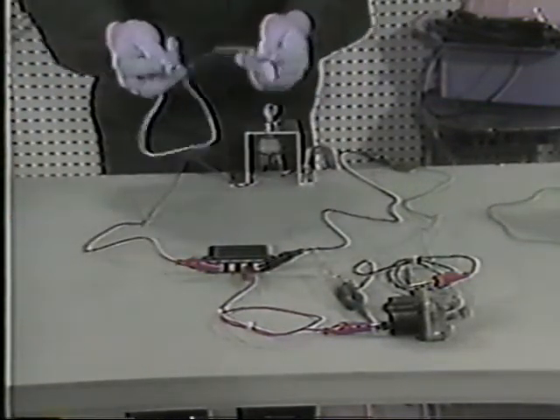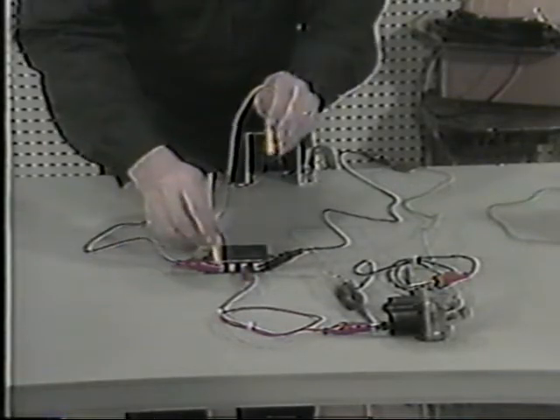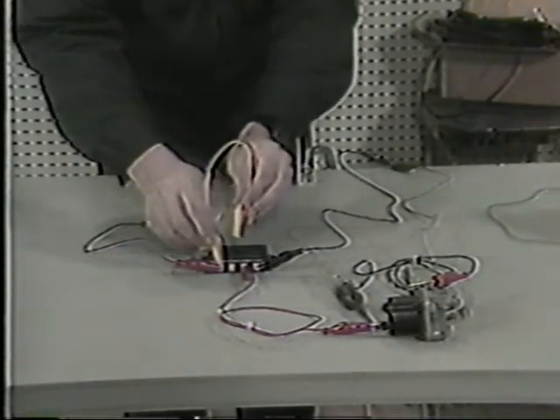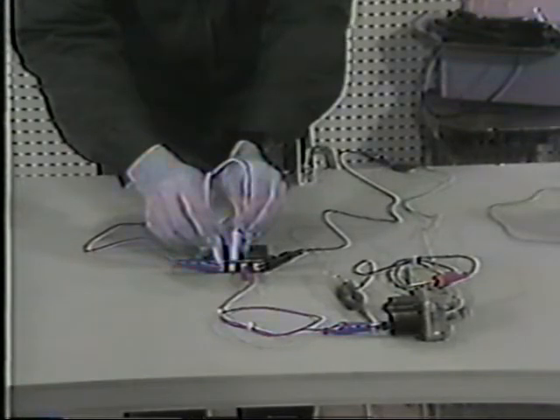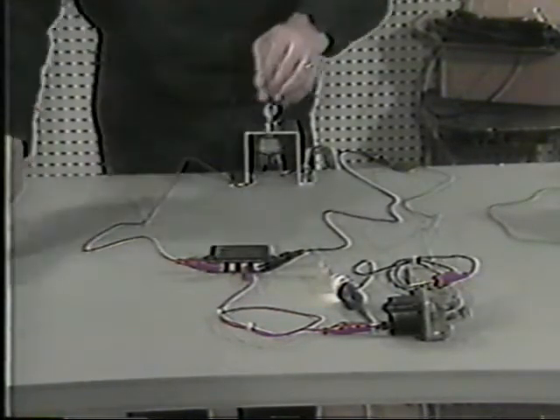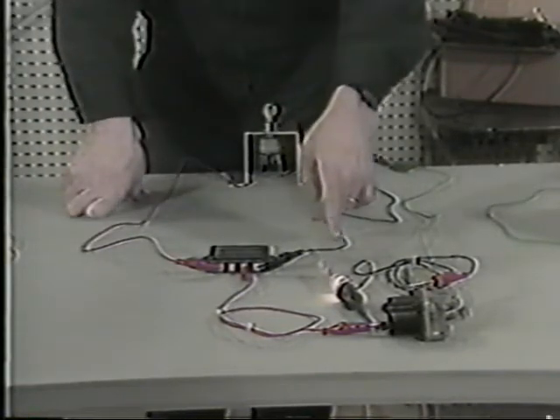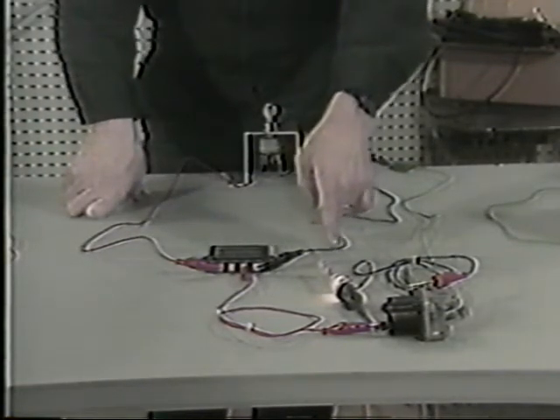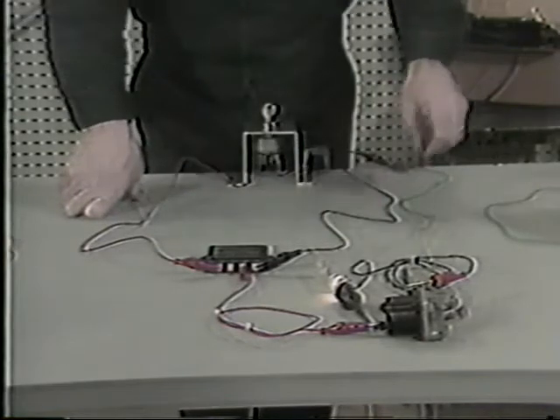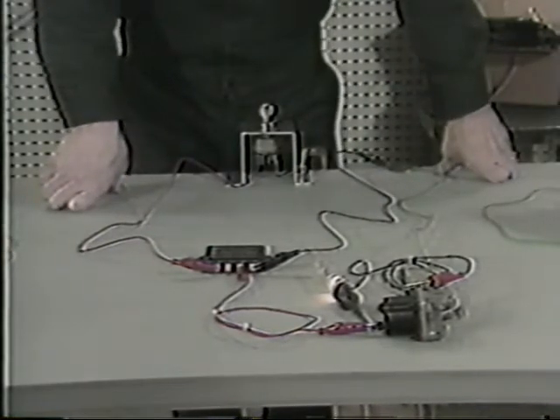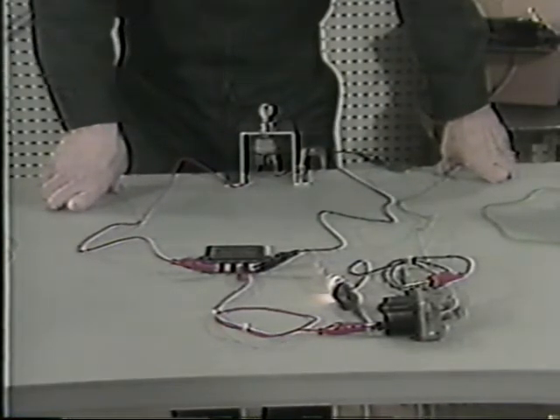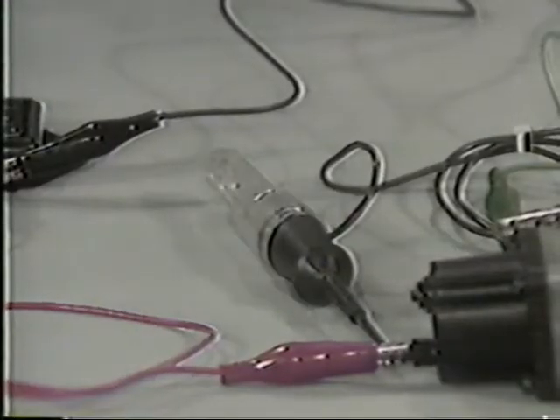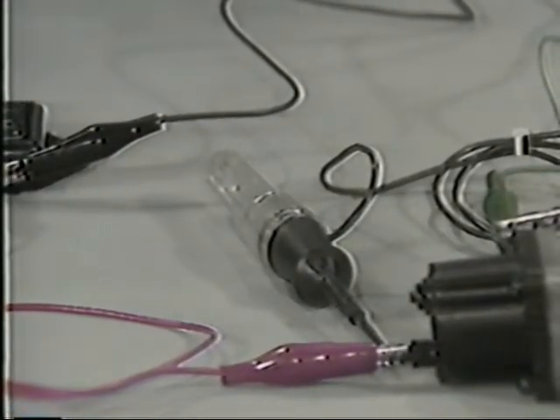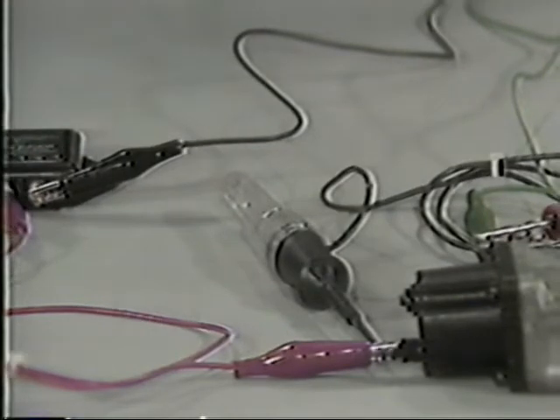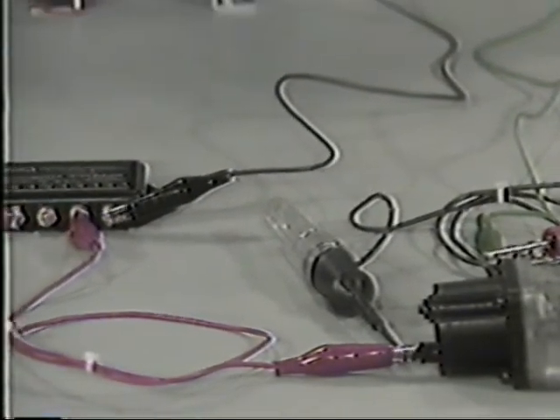Take a final jumper wire, connect it to post number 1, and briefly touch it to post number 2, simulating the start circuit input. The fuel solenoid should turn on, and the test light indicates that voltage has come up at that point. The voltage should remain for 20 to 40 seconds. At the end of that time, it should turn off. If the automatic override acts differently than described here, it has a problem.